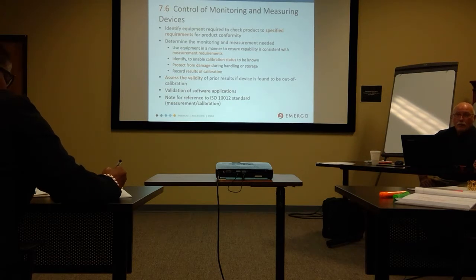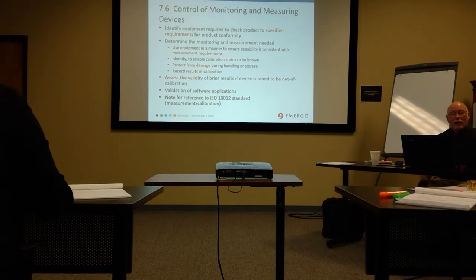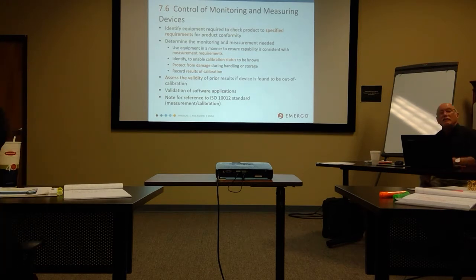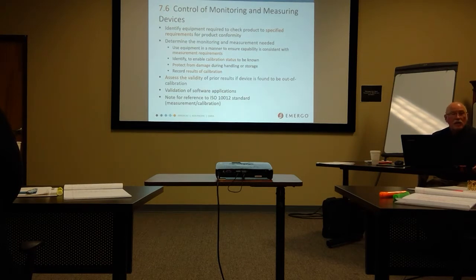Because "as found" is a big deal. Now, the calibration vendor's job, if they find it to be out of calibration, is to put it back in. Great, from this point moving forward, I'm okay, but I don't know anything about the past. So, investigation, risk assessment, what does this mean? Maybe nothing. Let's say you have a torque wrench that's used to put the final torque on something that holds that bed together. If that thing's out of calibration, what does it mean? Could be important, maybe not. Somebody has to make that determination.